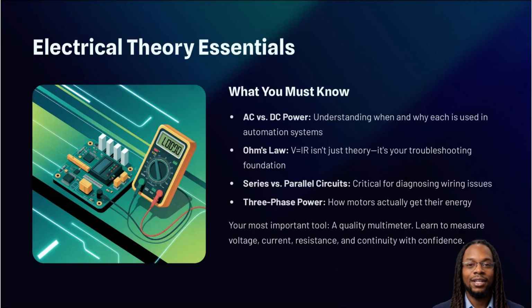It all starts with electricity. You need to be comfortable with two different worlds. First, there is high voltage AC, usually 120, 240, or 480 volts. This is the muscle. It powers the motors and the drives. Then there is low voltage DC, usually 24 volts. This is the nervous system. It powers the sensors and the controls.